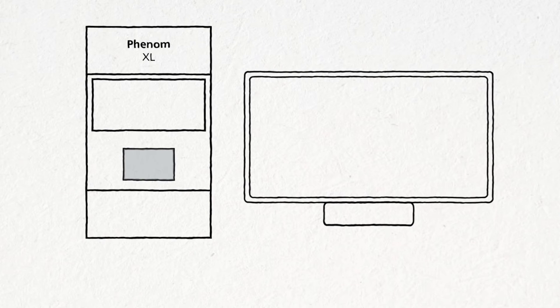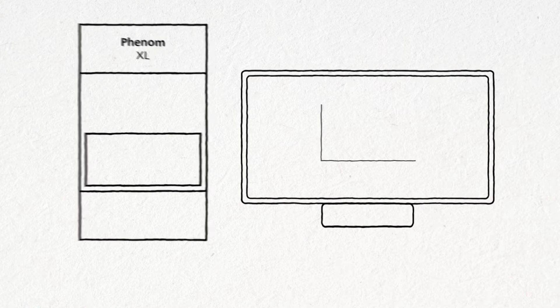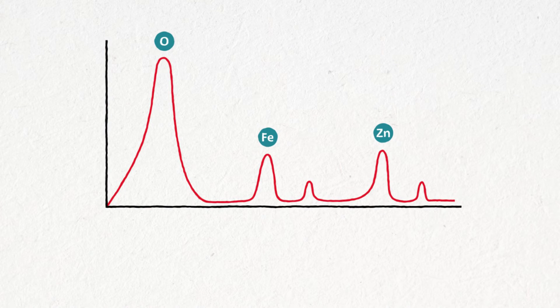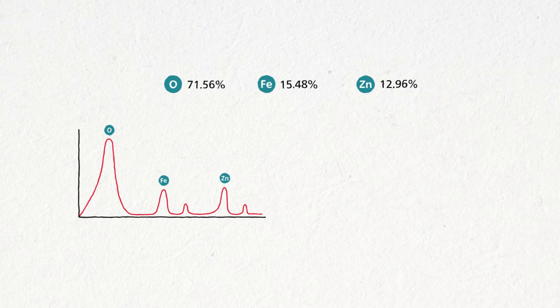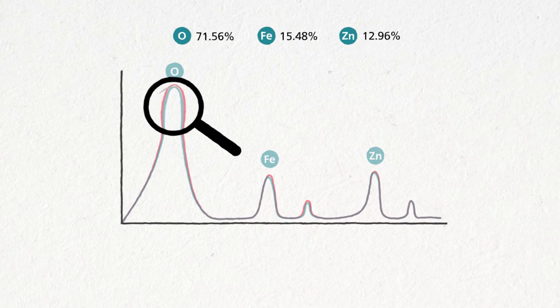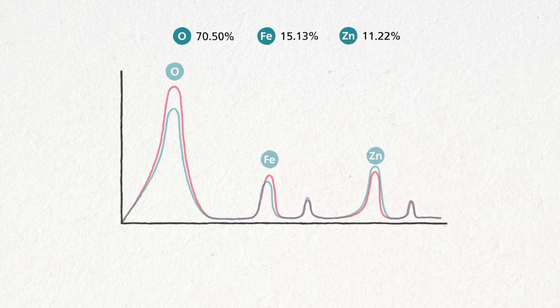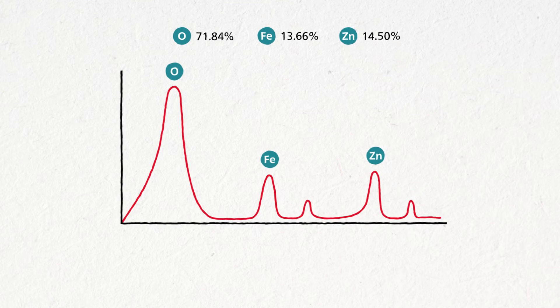The quantification mechanism in the Phenom is based on forward modeling. It works by analyzing which elements are present in the spectrum and providing a first quantification. Then a synthetic spectrum generator creates a spectrum based on that composition and matches it with the one that was measured during the analysis. By iterating and using different compositions, different spectra are generated and progressively compared with the measured spectrum until we get the perfect match, and that results in the quantification.